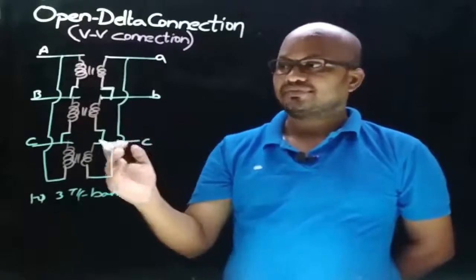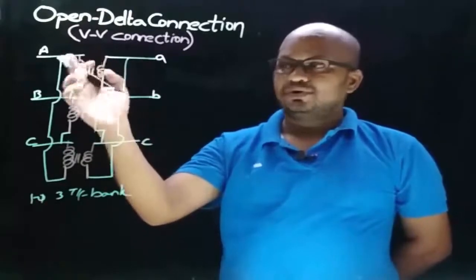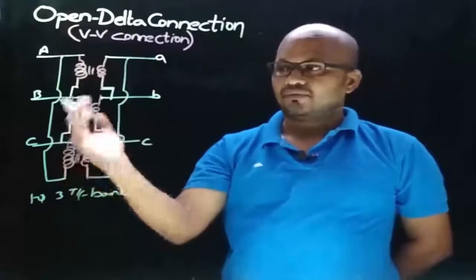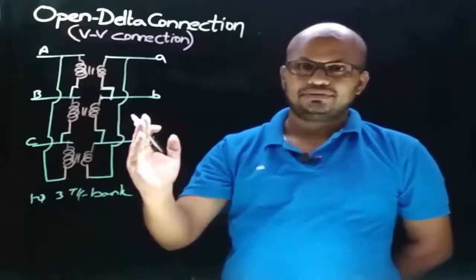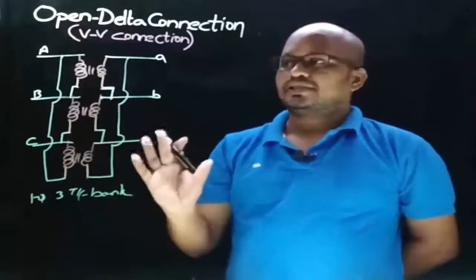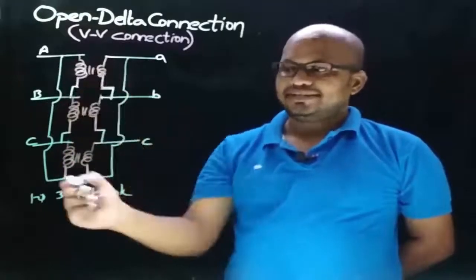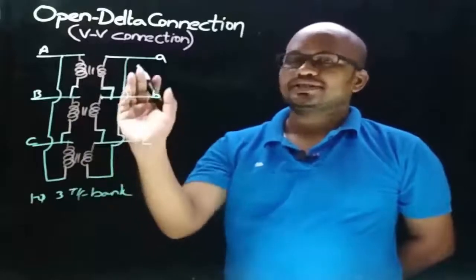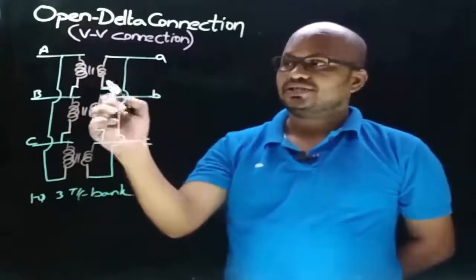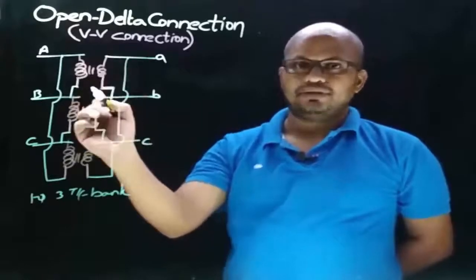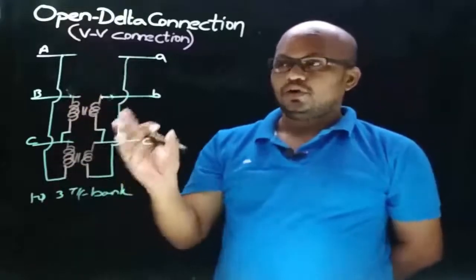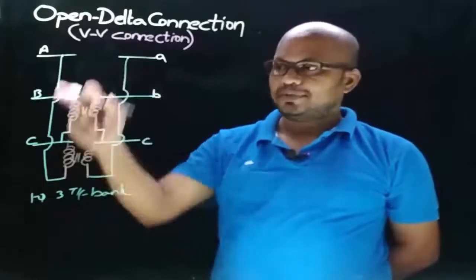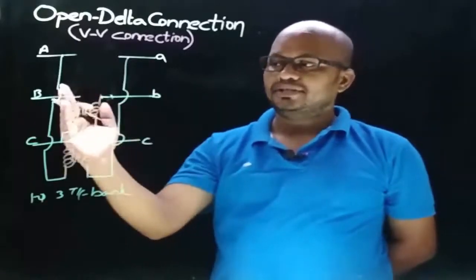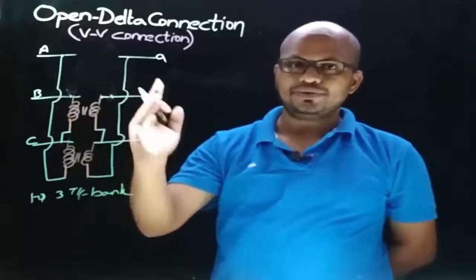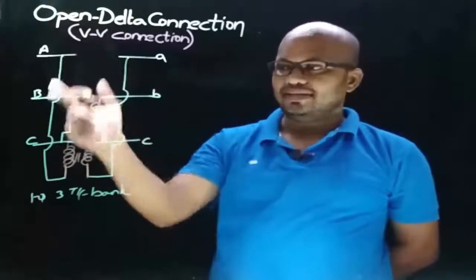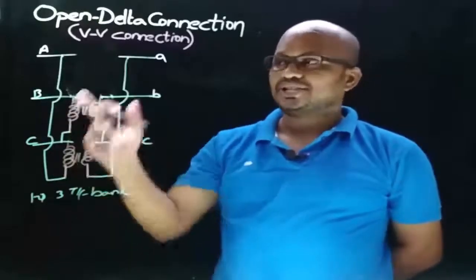Observe that here we are transferring 3-phase power, which has phase sequence ABC, from one circuit to another circuit, that is from the primary side to the secondary side. Let us suppose that this transformer in this bank got failed. So now let's observe the resultant winding connections by removing this transformer from this bank. Now observe that after removing transformer 1 from this bank, still we can maintain the 3-phase supply from the primary side to the secondary side.